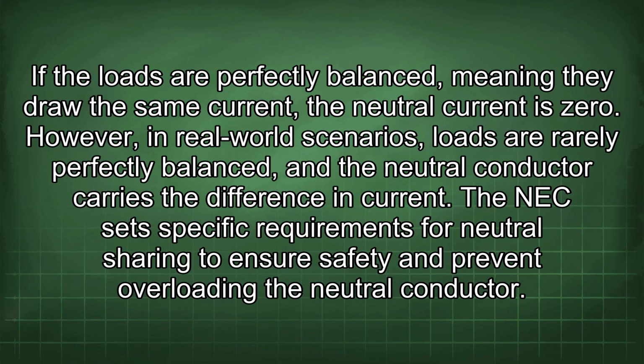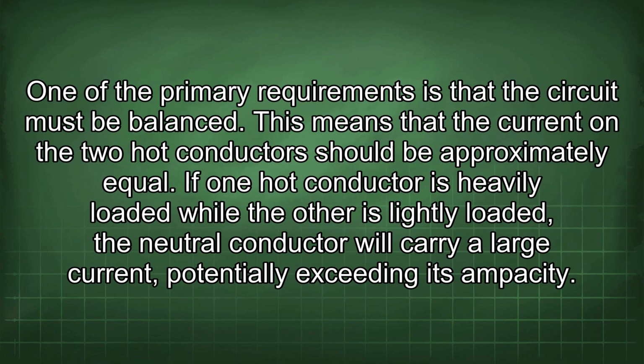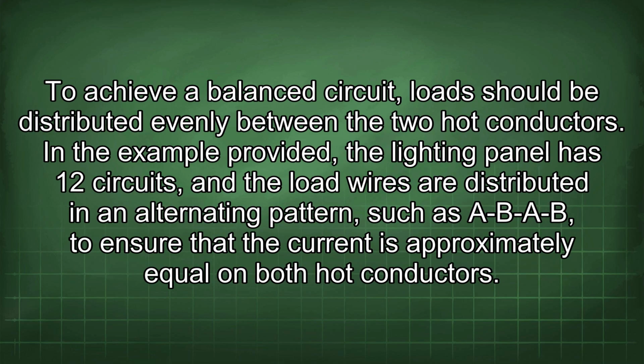The NEC sets specific requirements for neutral sharing to ensure safety and prevent overloading the neutral conductor. One of the primary requirements is that the circuit must be balanced. This means that the current on the two hot conductors should be approximately equal. If one hot conductor is heavily loaded while the other is lightly loaded, the neutral conductor will carry a large current, potentially exceeding its ampacity. To achieve a balanced circuit, load should be distributed evenly between the two hot conductors. In the example provided, the lighting panel has 12 circuits, and the load wires are distributed in an alternating pattern, such as A-B-A-B, to ensure that the current is approximately equal on both hot conductors.